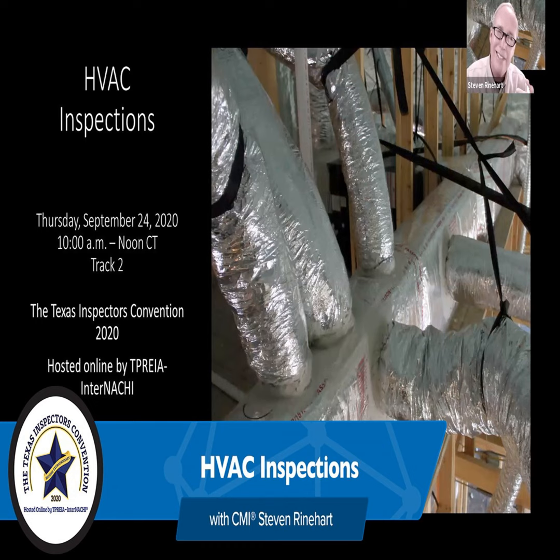And you get that with the old solid duct in houses 60 years ago, 3 and 12 pitch, not a lot of space to crawl around in an attic, and you're usually crawling over it. You will find, more often than not, rigid duct that's kind of oval shaped. It's not supposed to be oval. If it's oval, it may restrict flow. So we've got to note damage in that ductwork.